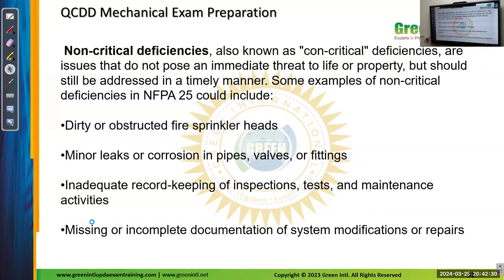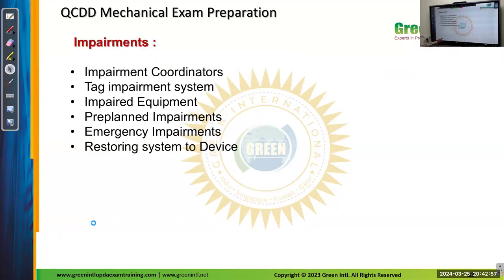Non-critical deficiency is a minor observation. It is an observation, of course, but QCDD will pass with comments. You have to rectify these comments. So, also known as non-critical deficiencies, examples include dirty or obstructed fire sprinkler heads, minor leaks, inadequate record keeping of inspection, testing, and maintenance, and missing or incomplete documentation of system modifications or repairs. So impairments, impairment coordinators, tag impairment systems, we will see each in detail.